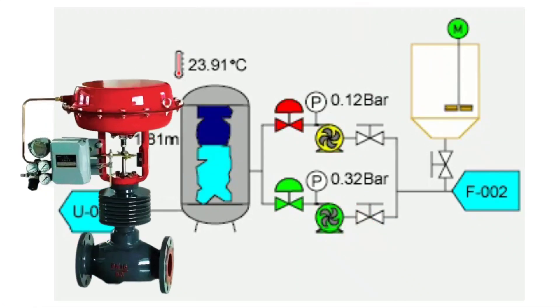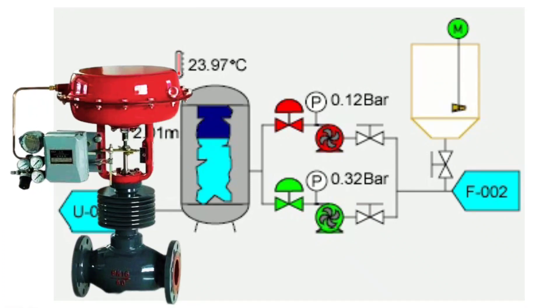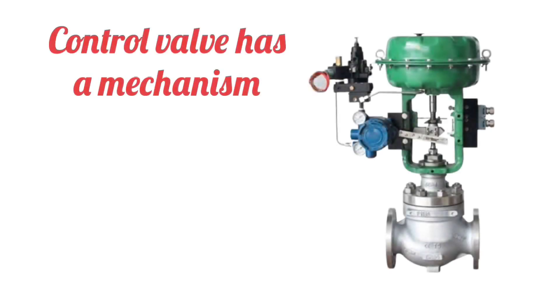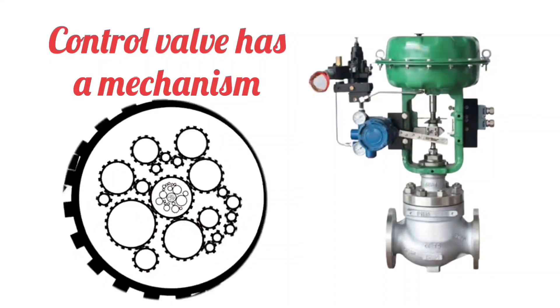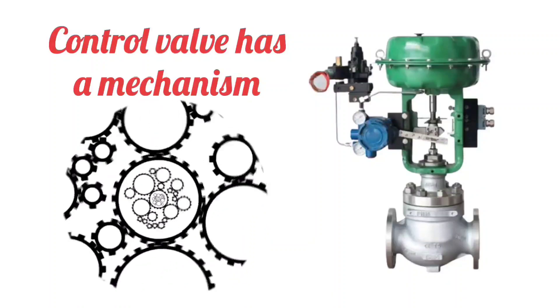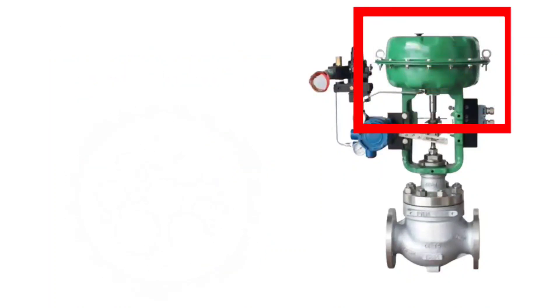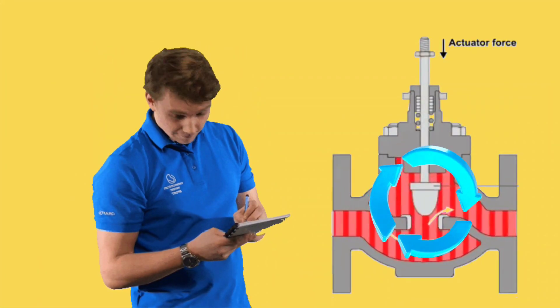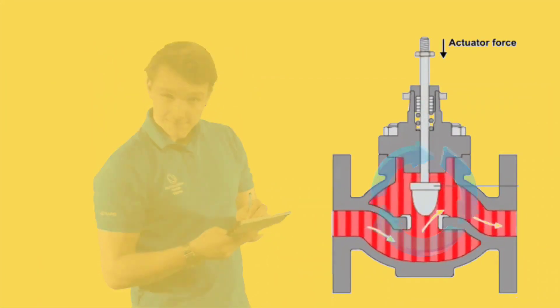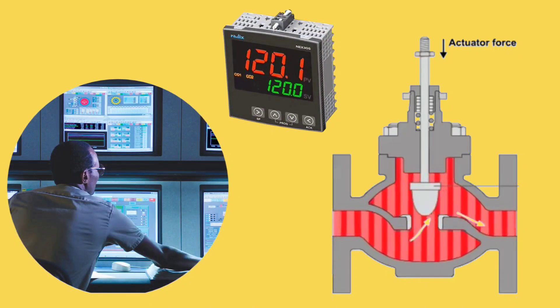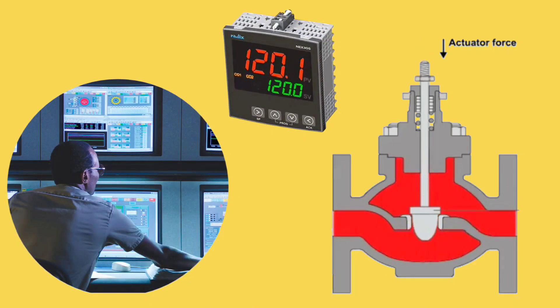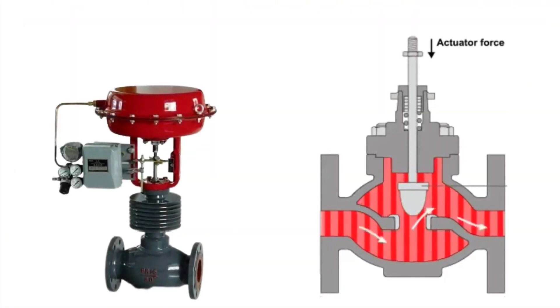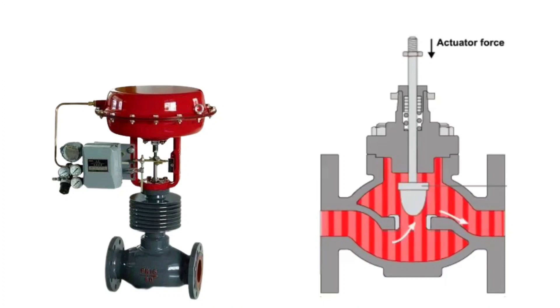And with the help of control valves, the values of these parameters can be reduced or increased. In control valves, there is a mechanism — the upper part of the control valve, which is called the control valve actuator. It adjusts the position of the plug or disc according to the signal received from the controller, and controls the flow of fluid. Control valves are used where precise control is necessary.